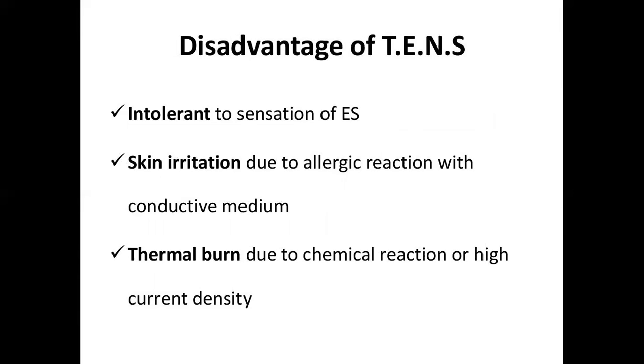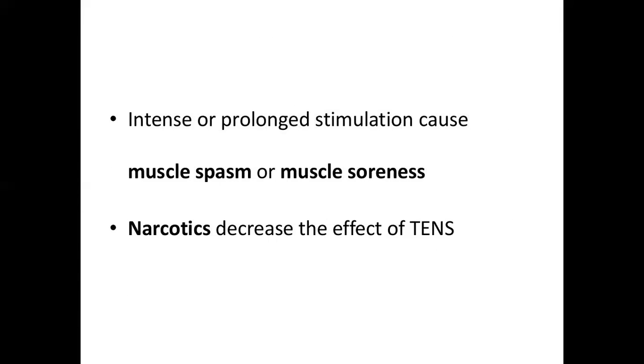Disadvantages of TENS. Intolerance to the sensation of electricity, skin irritation due to allergic reaction with the conductive medium, thermal burn due to chemical reaction or high current density. Intense or prolonged stimulation causes muscle spasm or muscle soreness. Narcotics decrease the effect of TENS.